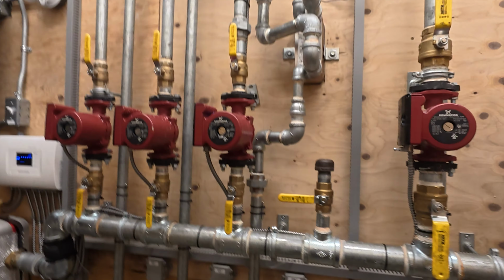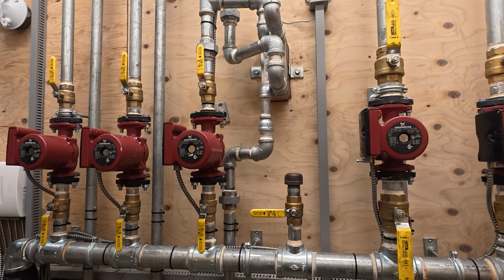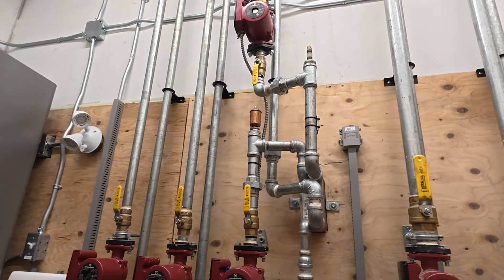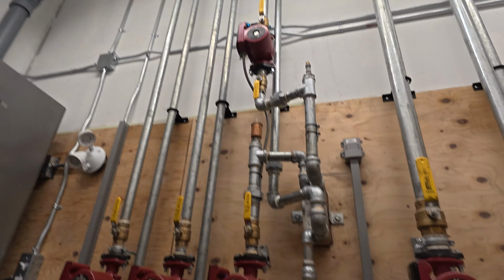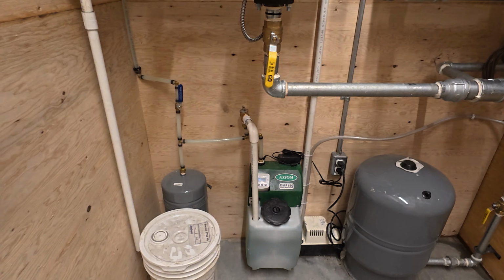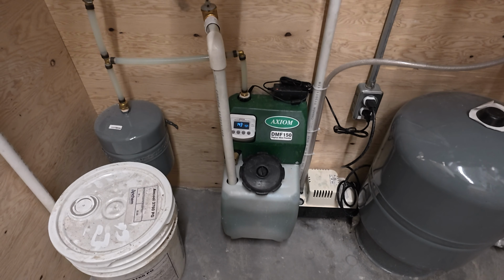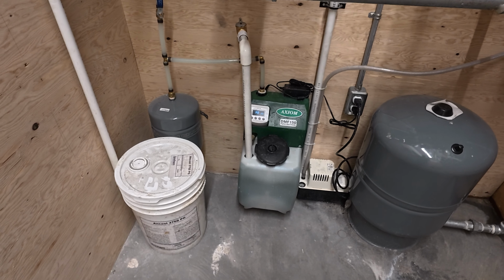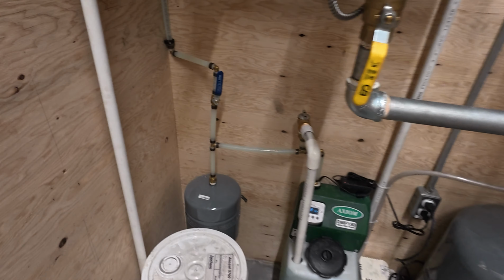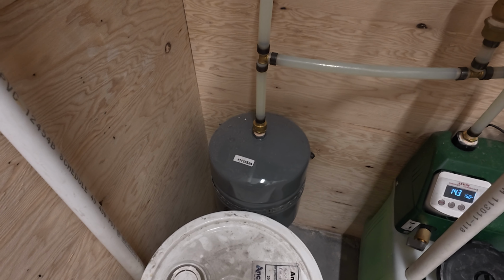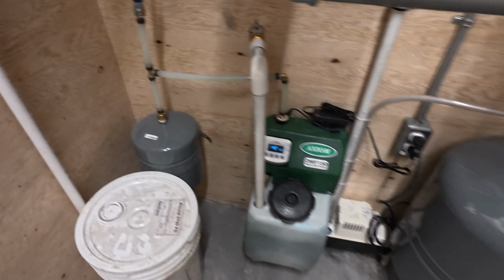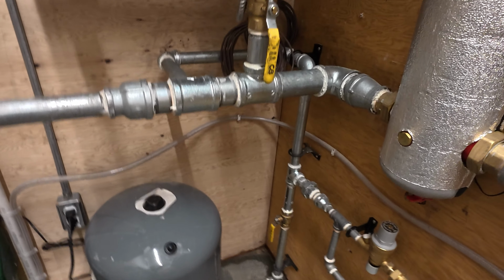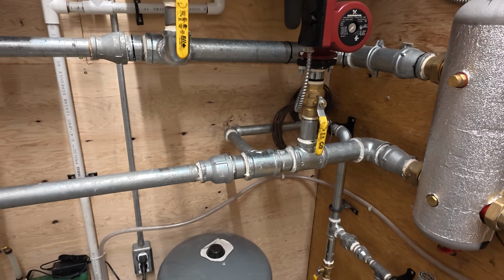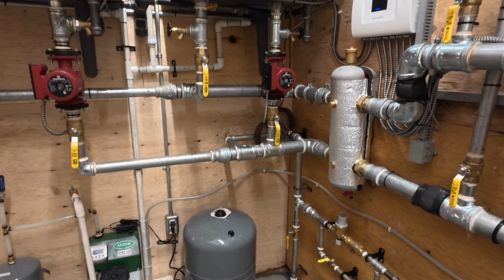So we got a pump—it pumps it into a heat exchanger, tiny little heat exchanger. The heat exchanger then pumps it through and goes out and back to the snow melt over there. We got our pump that just pumps into the snow melt and keeps it pressurized with a little expansion tank. Then we got our main expansion tank, ties up and in and ties into our main boiler loop.